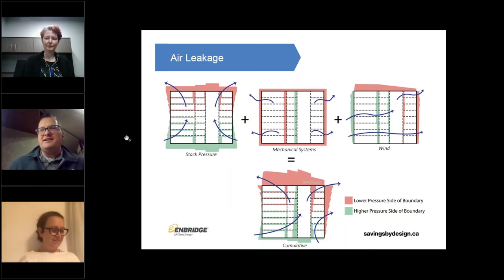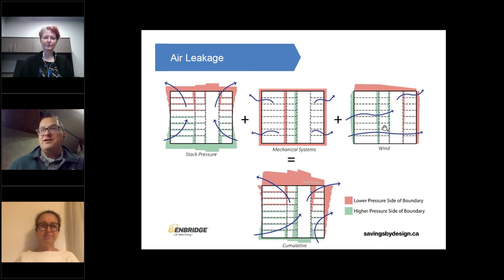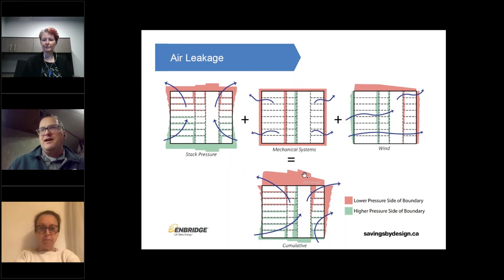Today we're going to be talking about air leakage with a focus on stack effect, compartmentalization, and indoor air quality impacts. You basically need holes that air can go through and pressures that drive the air through those holes. On the left you have stack pressure — hot air rises — illustrated in wintertime. Mechanical systems are often pressurizing corridors and overall pressurizing the building. Wind effects can vary greatly depending on exposure. When all of those are combined, stack effect rules the day to some extent, where air is being pushed up the building and outward.